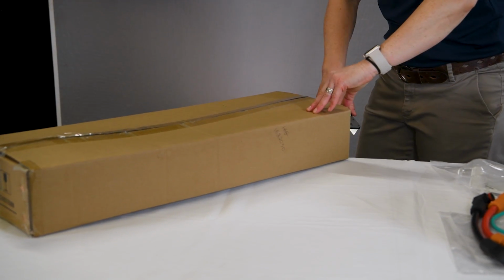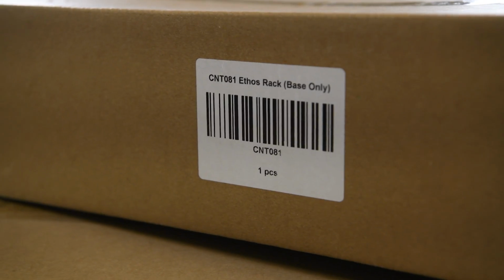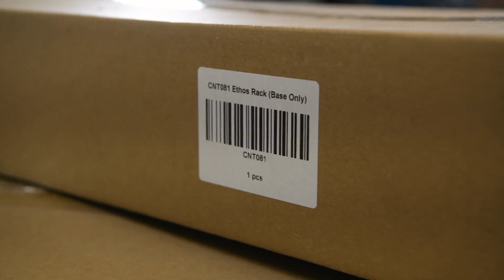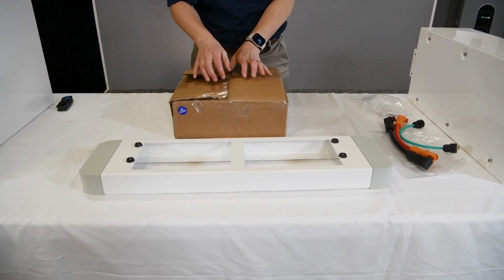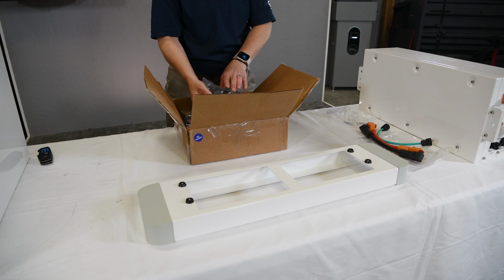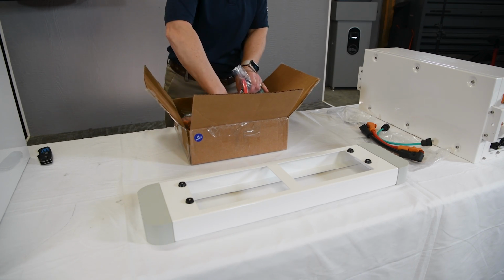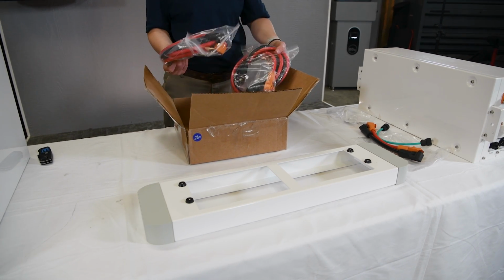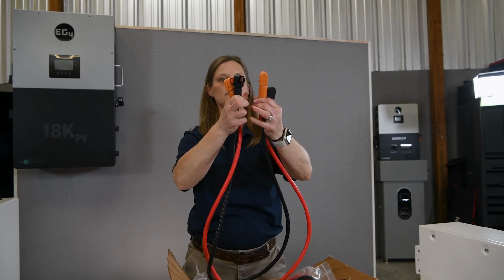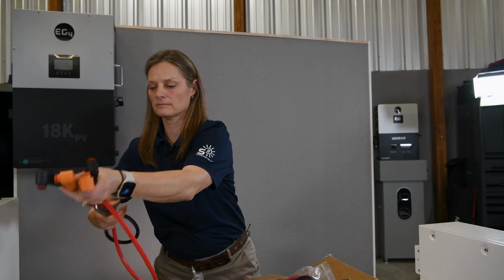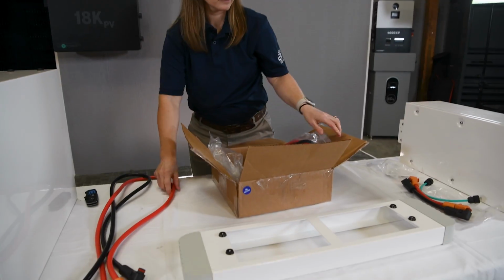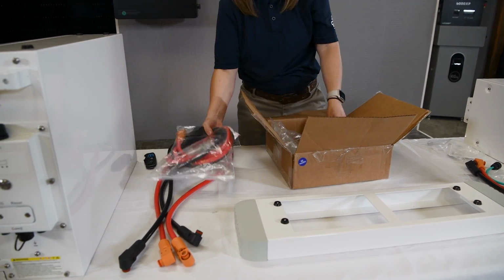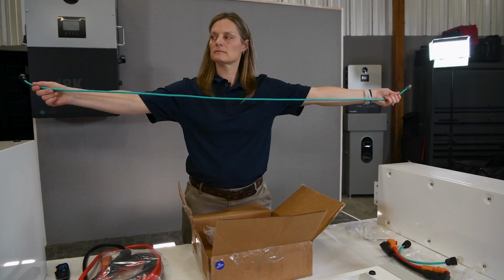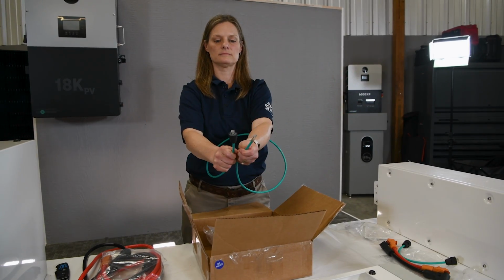Inside this longer box, you'll discover the additional rack base designated for our second stack of batteries. And moving on to our final box, it contains our extra cables for connecting our stacks. Here we have two sets of 4.9-foot battery cables, each equipped with Amphenol connectors on both ends intended for paralleling our two stacks of batteries. Additionally, there's a 4.9-foot communications cable included. The installation is designed to be quick and easy, so let's get started.